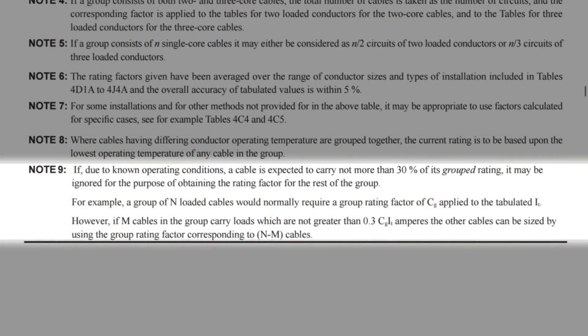The note continues: for example, a group of n loaded cables would normally require a group rating factor of Cg applied to the tabulated It. However, if m cables in the group carry loads which are not greater than 0.3 × Cg × It amperes, the other cables can be sized by using the group rating factor corresponding to n minus m cables.